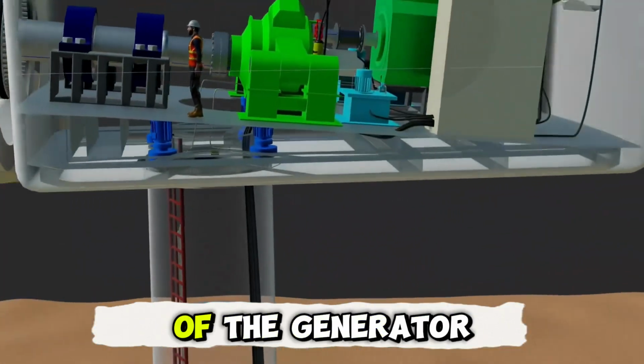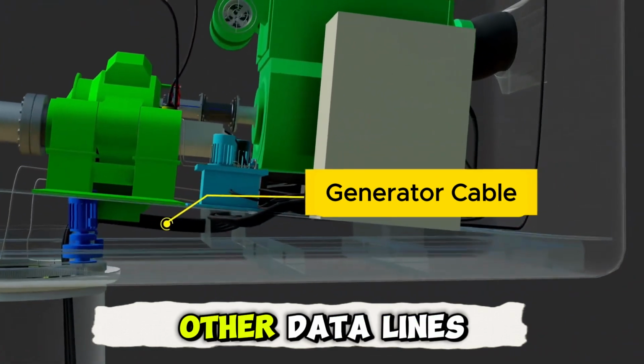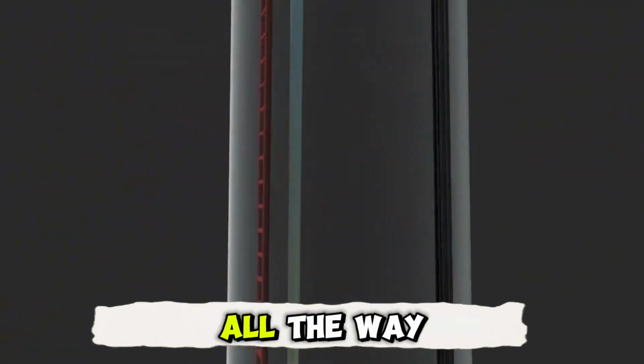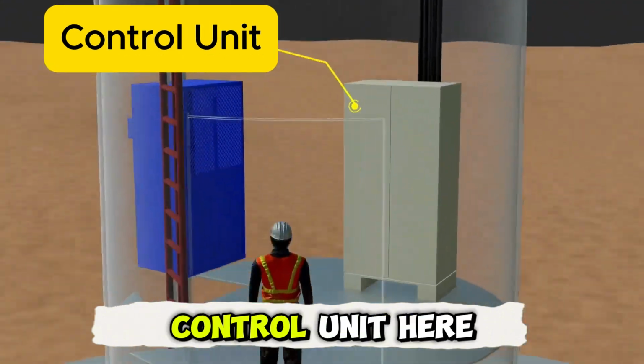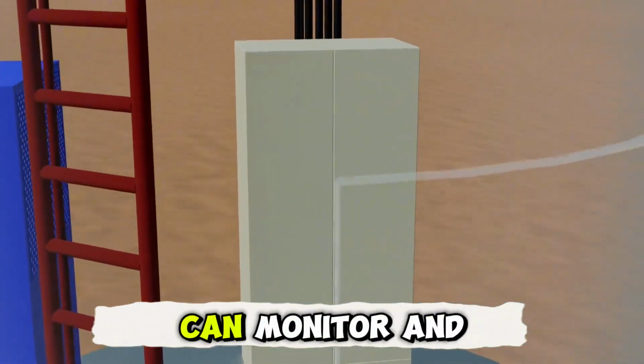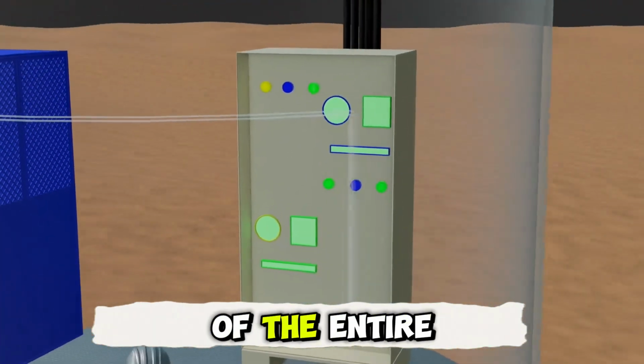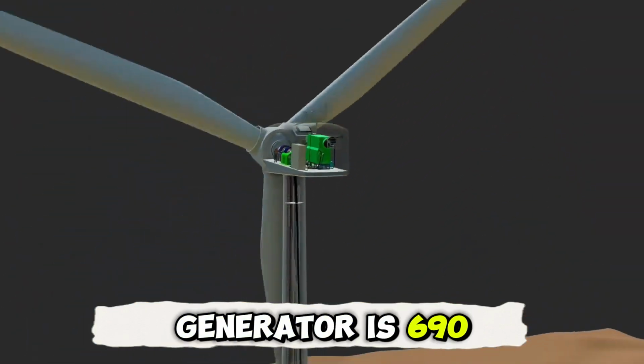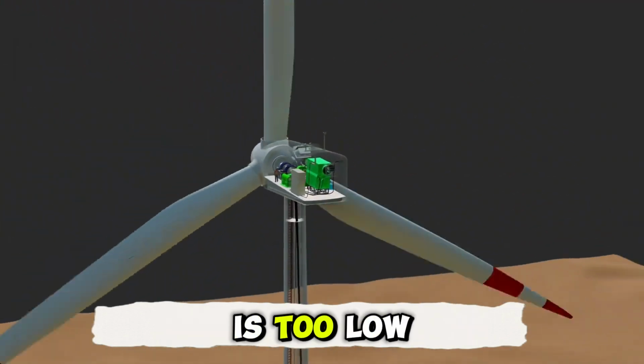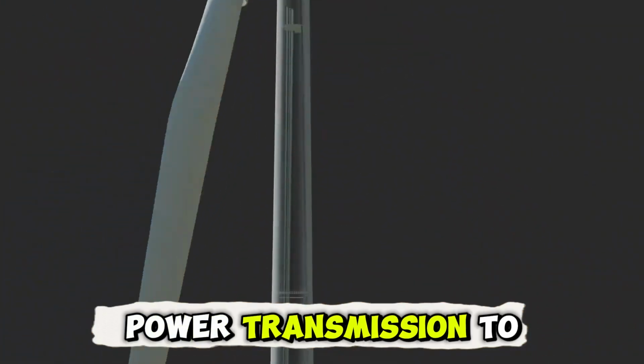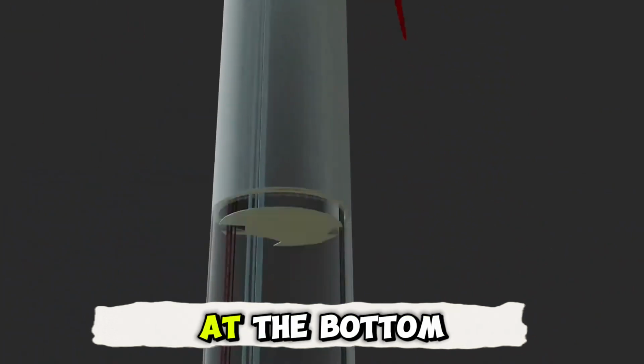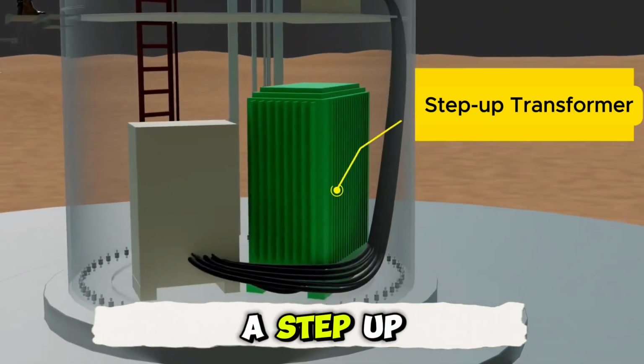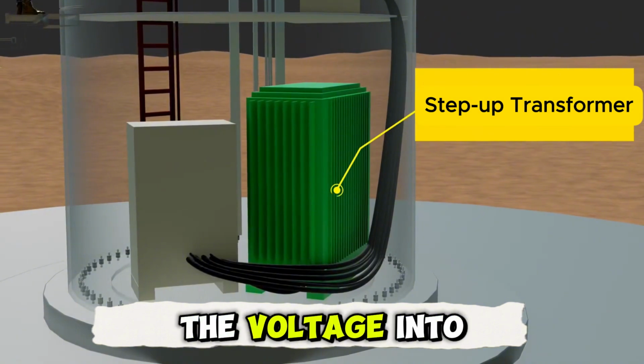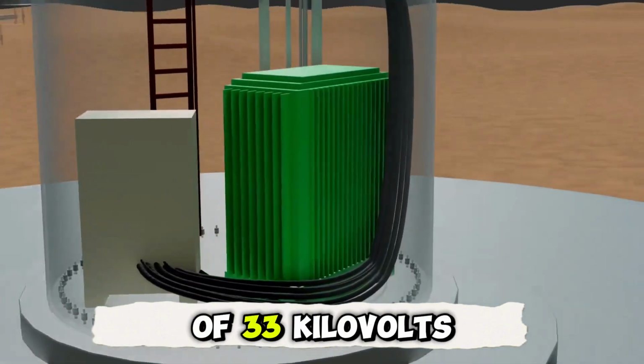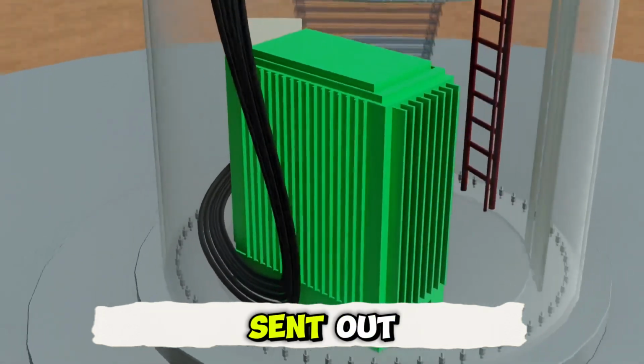The power lines of the generator, control lines, or other data lines will pass through the tower all the way down to the bottom. There is a control unit here. The control unit can monitor and control the operation of the entire wind turbine. Since the voltage generated by the generator is 690 volts, this voltage is too low to perform long-distance power transmission. To solve this problem, at the bottom of the tower, there is also a step-up transformer. It can convert the voltage into a high voltage of 33 kilovolts before finally being sent out.